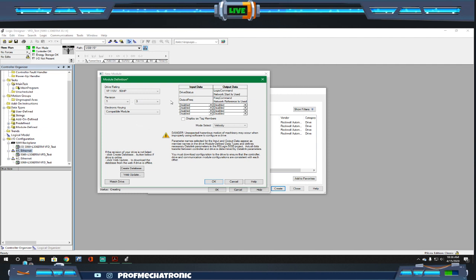Now over here, you're going to see 2 other columns. We have an input data and an output data. What input data and output data are used for is to actually be able to take some of the data that exists inside of these drives and bring it to the PLC. So that's input to the PLC. We're also able to send certain information out to the drive itself, so we call that output data. At this point, we're not going to cover all of the many options that you have there. We'll do that in a subsequent programming Ethernet IP VFD live stream. But right now, just understand that input data and output data are how we can share information between the PLC and the drive.